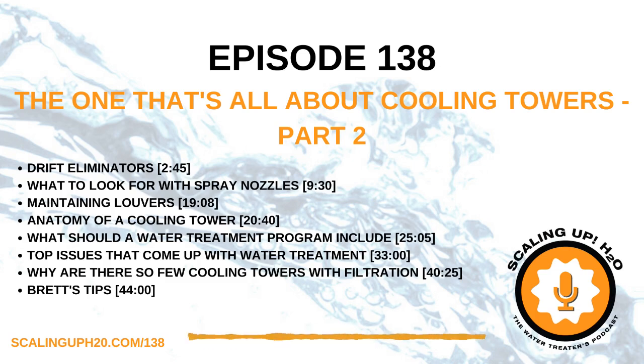What can we do about that? Our general rule of thumb on open cooling towers is we can typically turn those down 50%. So if you're rated for 1,000 GPM flow rate, you can turn it down on that same unit to 500 gallons per minute and still be good.